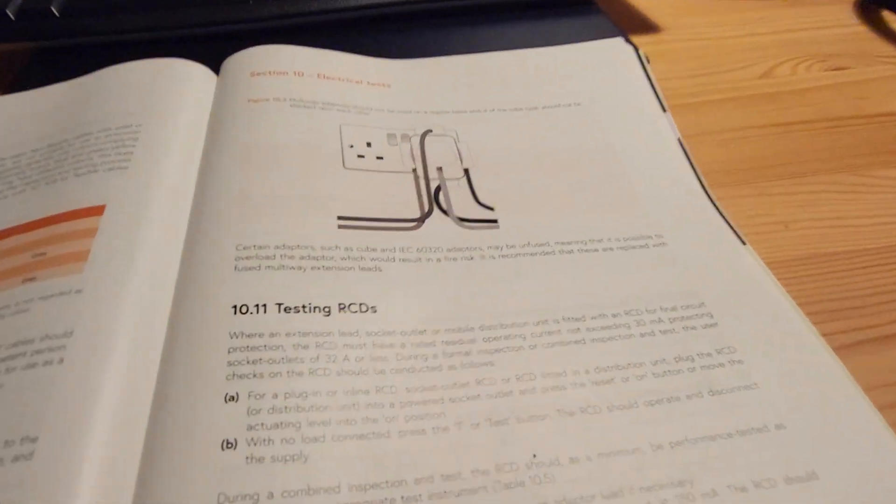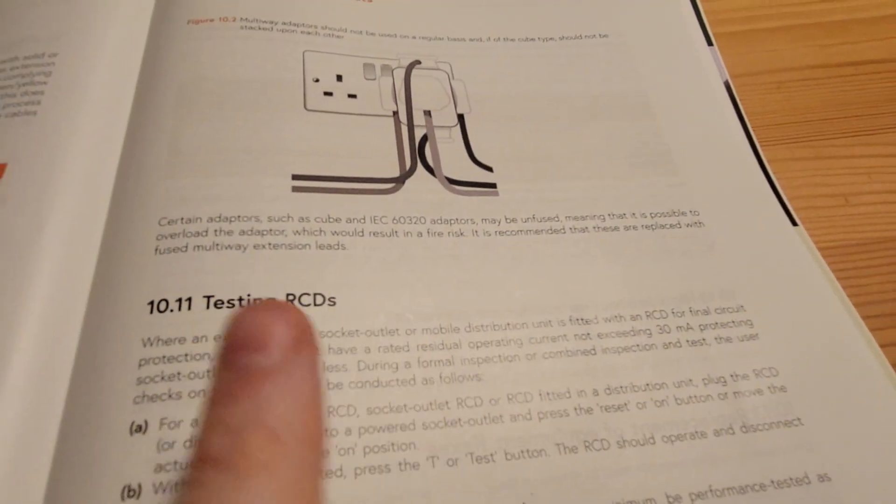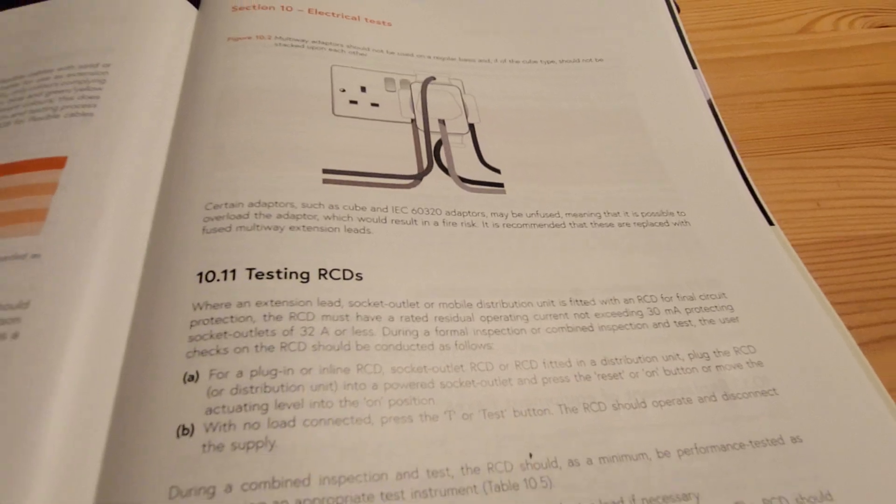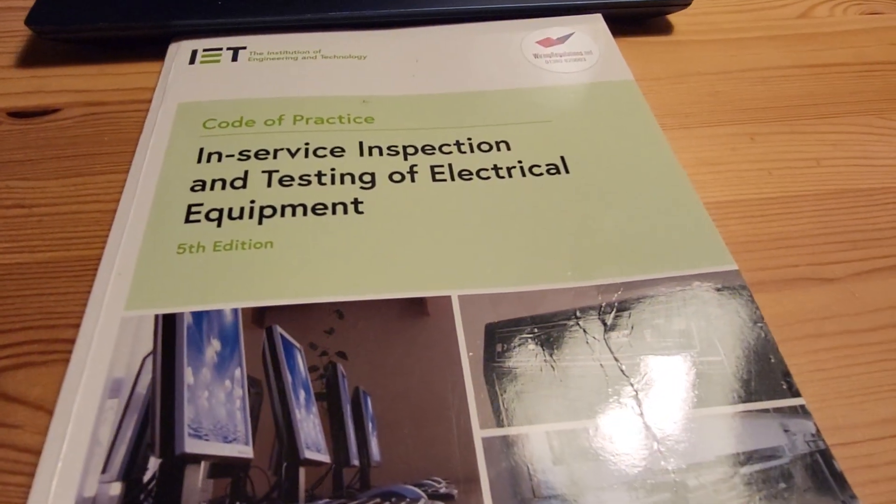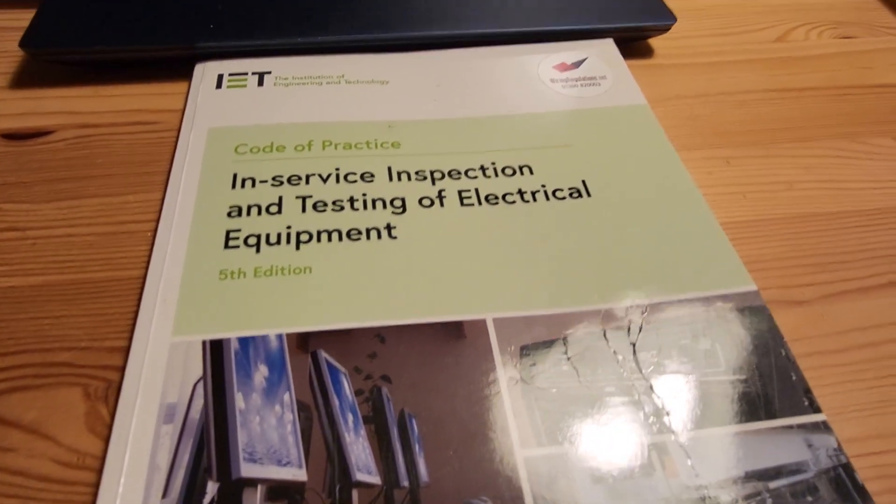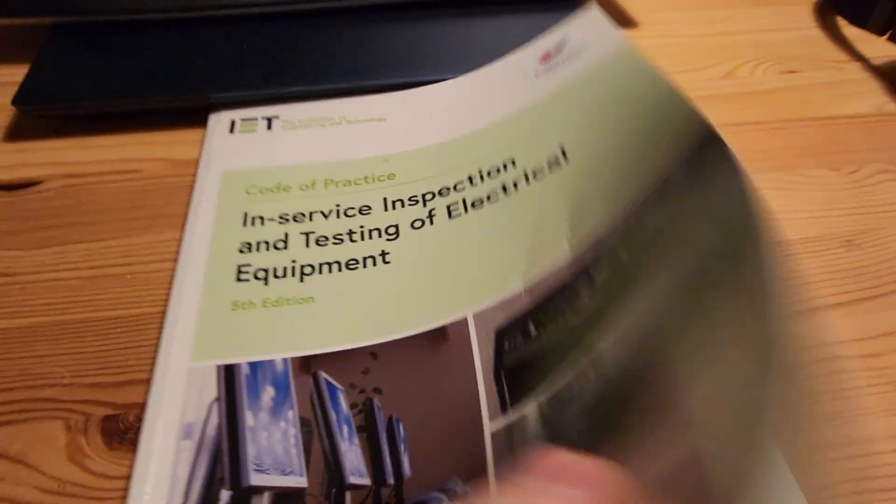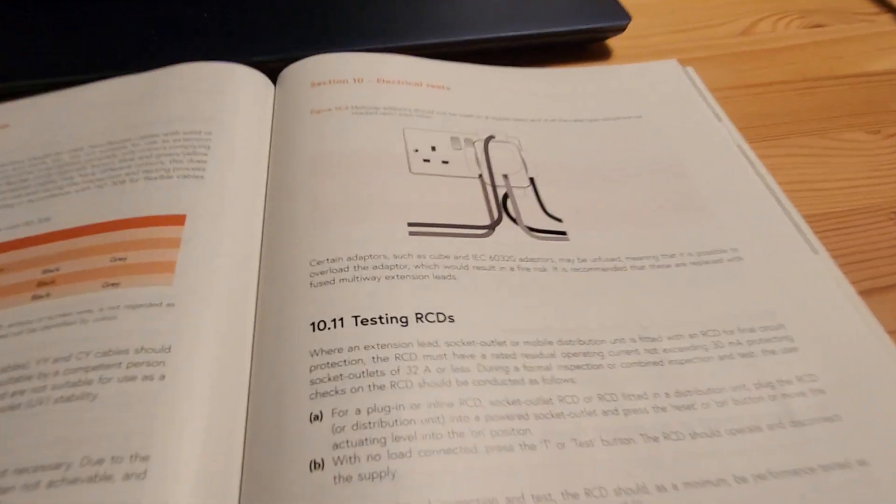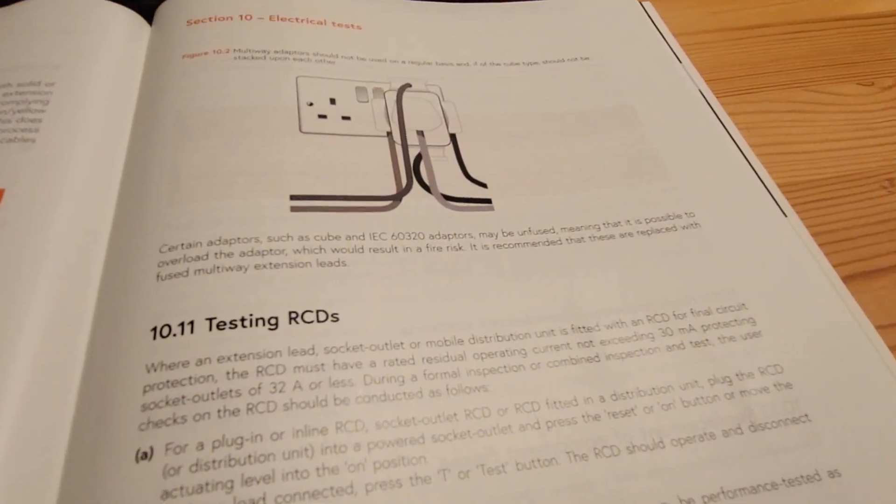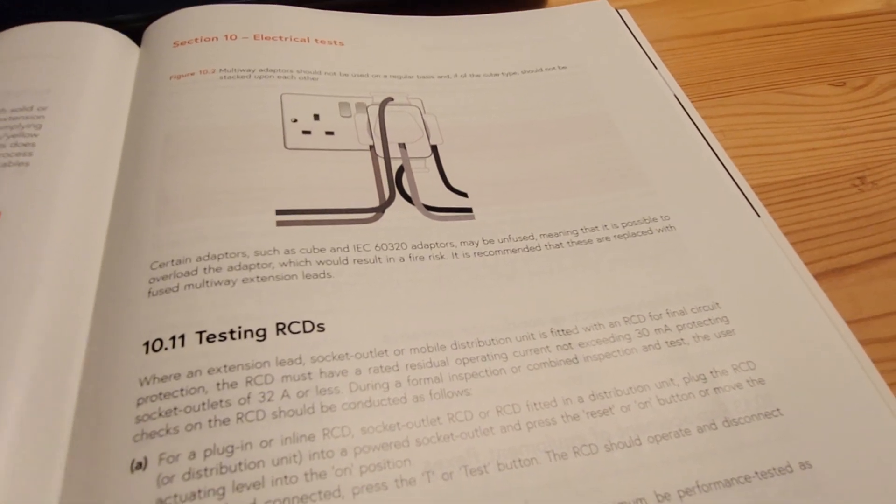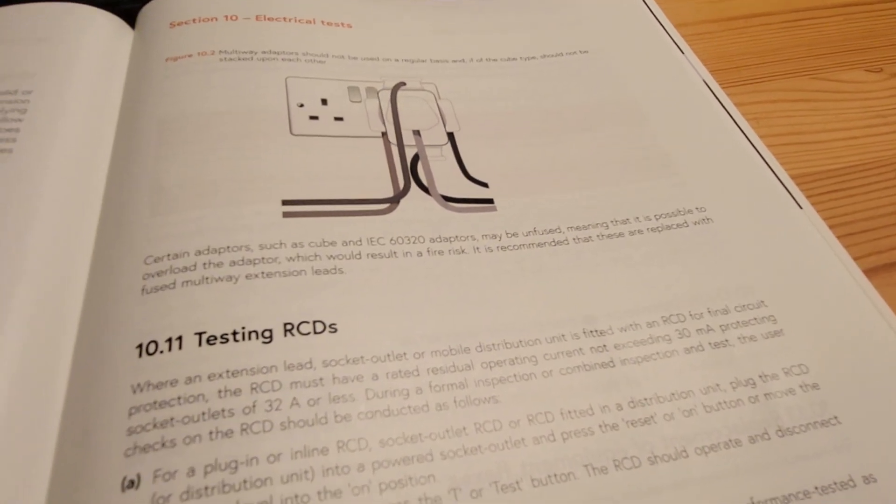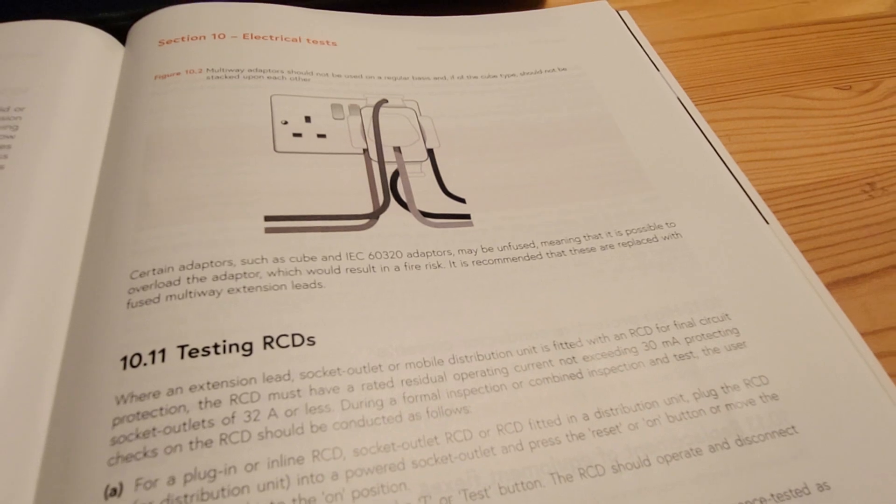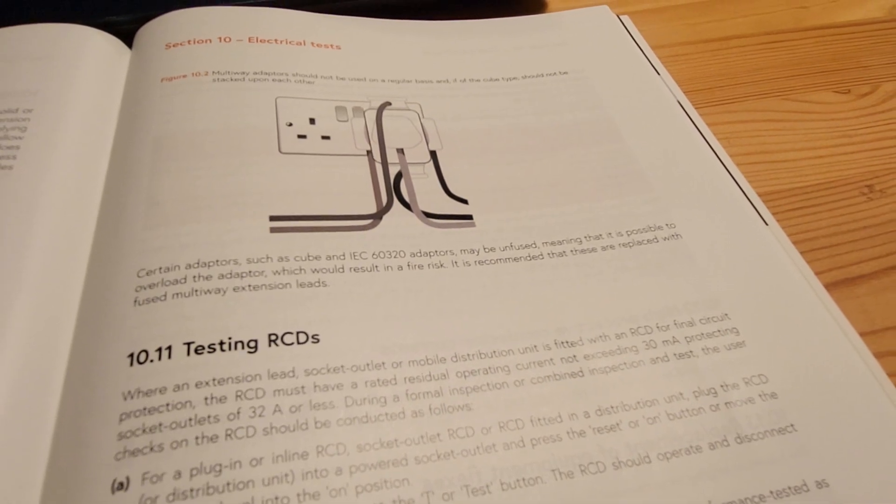So what does the code of practice say? Well, the code of practice says here, this is the, just for those of you who want to know, it's the in-service inspection and testing of electrical equipment, fifth edition. So this is the most recent one, and it says here, certain adapters, such as cube adapters, which is what this is, or IEC adapters, may be unfused.